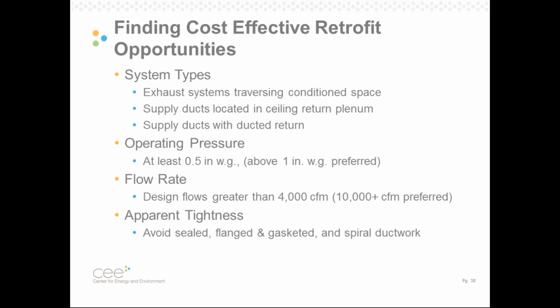System types, I've talked about this already, but we look for exhaust systems traversing conditioned space, supply ducts located in ceiling return plenum, and supply ducts with ducted returns. I mentioned earlier that pressure drives leakage, so we want higher pressure systems in order to find higher leakage. We say a minimum of 0.5 inch water column, and we'd prefer over 1 inch of water column. And then again, leakage requires flow rate. We need to set a minimum floor for the size of these systems so that it justifies bringing out a crew and sealing them. So we say we like systems greater than 4,000 CFM, and we prefer 10,000 CFM. And again, apparent tightness: if a duct looks sealed, it probably is. This isn't to say the opposite, that if a duct looks leaky, it is leaky, but we can rule out systems that look tight.